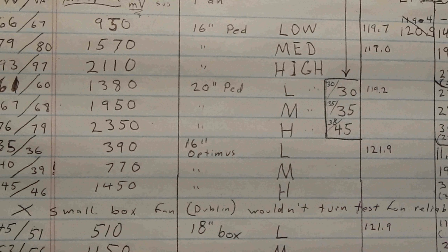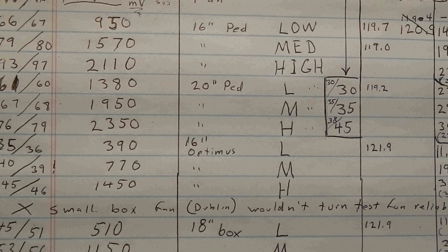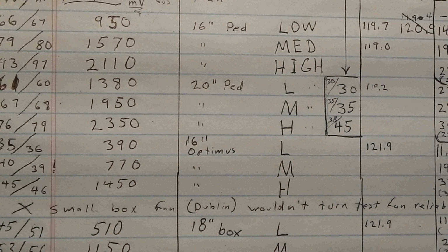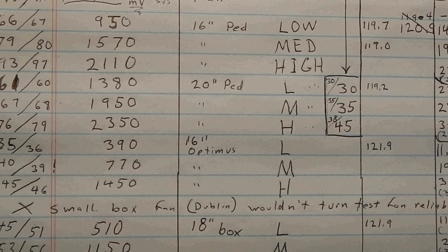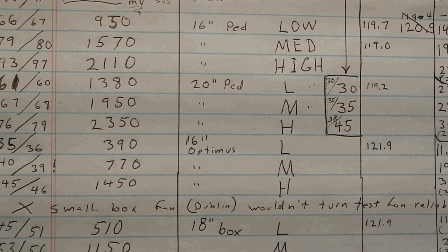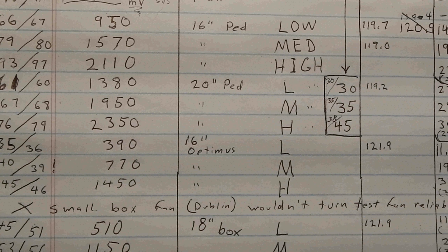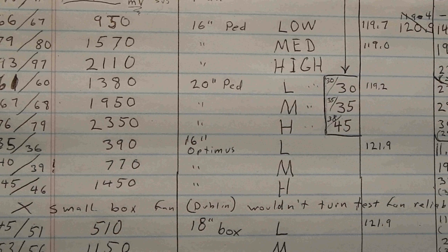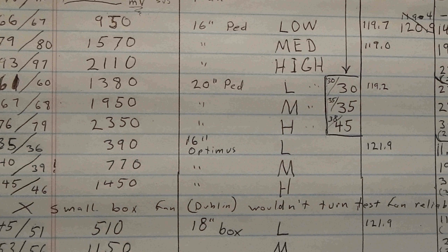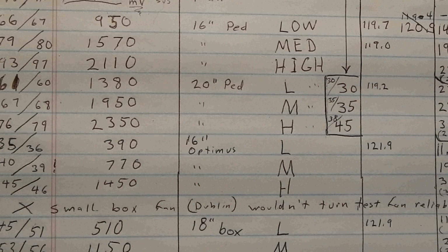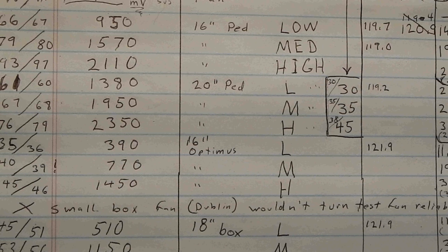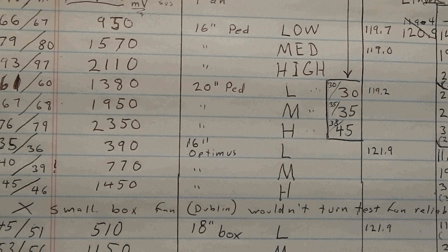And I had done a quick look at these two fans, and granted, these two fans aren't quite as bad in terms of differences, but these two fans, holy moly, this one's damn near a factor of 3 in terms of efficiency, being much better at high speed than it is at low speed. So it really does carry out what I said. These fans are pretty inefficient at low speed, and some are worse than others, so that kind of gets his argument, but they're all pretty bad at low speed.